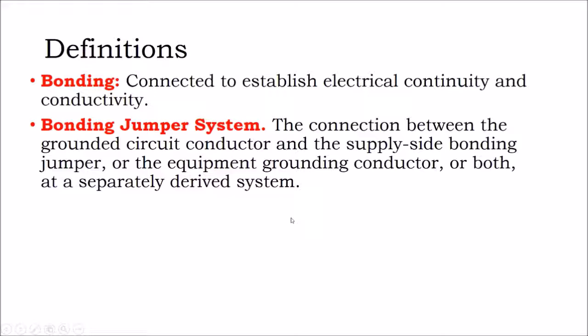Bonding: connected to establish electrical continuity and conductivity. So the question is, well, what's the difference between bonding and grounding? And the answer is there is not much difference. Bonding is a continuous path between two things, and all of your metal parts are bonded together, and all of your metal parts are attached to that equipment grounding conductor.